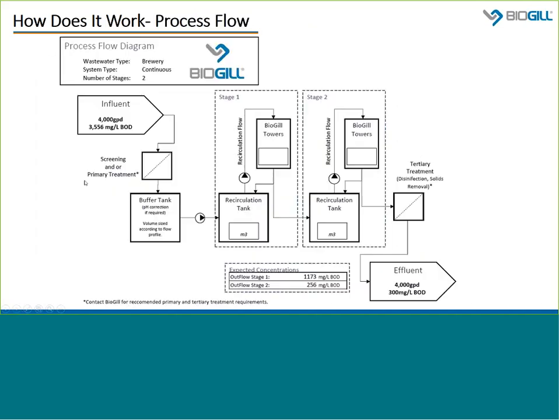We can see how it's put together as a system, not unlike any wastewater treatment system. In this case, it was a projection model we did for a brewery where the daily flow was 4,000 gallons per day at about 3,500 milligrams per liter BOD. Following some screening or primary treatment — in this case a density-based method — it goes into an equalization tank where pH is corrected, then through two stages of BioGill towers and recirculation tanks, finally discharging through tertiary treatment as required by local authorities. Most of our clients are looking for about 90% reduction in BOD, or sometimes to get below 300 milligrams per liter BOD.